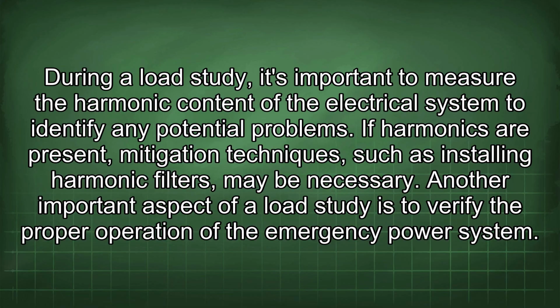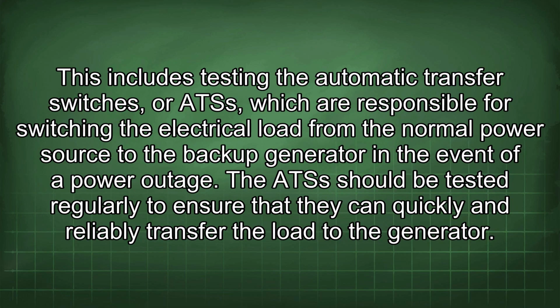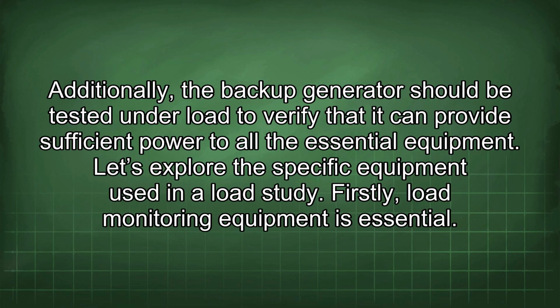Another important aspect of a load study is to verify the proper operation of the emergency power system. This includes testing the automatic transfer switches, or ATSs, which are responsible for switching the electrical load from the normal power source to the backup generator in the event of a power outage. The ATS should be tested regularly to ensure that they can quickly and reliably transfer the load to the generator. Additionally, the backup generator should be tested under load to verify that it can provide sufficient power to all the essential equipment. Let's explore the specific equipment used in a load study.